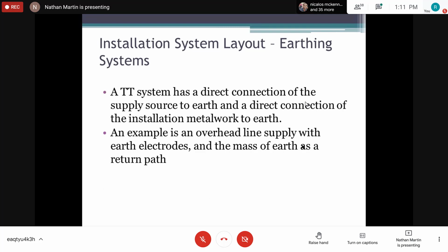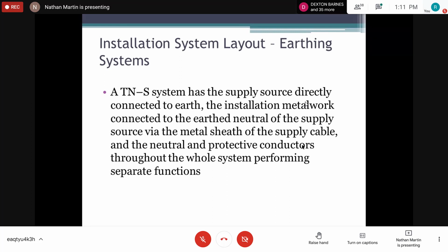A TT system has a direct connection of the supply source to earth and a direct connection of the installation metalwork to earth, meaning that the metal conductive parts in a building are directly linked to the earthing electrode. So an example is an overhead line supply with earth electrodes and a mass of earth as a return path, right? Now, a TN-S system, right? So the TN-S system has the supply source directly connected to earth. The installation metalwork is connected to the earth neutral of the supply.